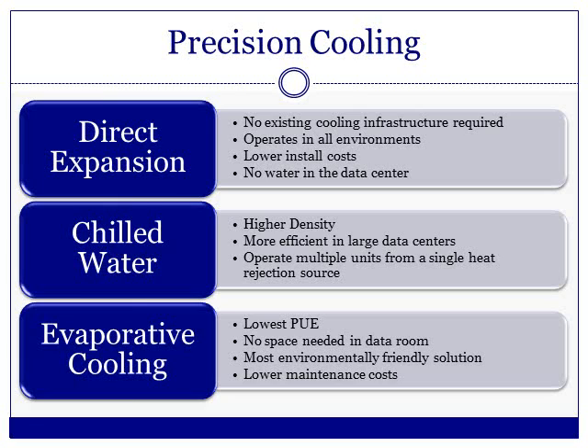A third, relatively new cooling method to be utilized in the data center is evaporative cooling. This is most effective in climates with cooler temperatures and low relative humidity. Evaporative cooling is efficient and has the lowest PUE, and does not require any floor space within the data center.